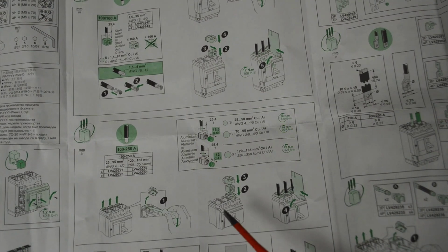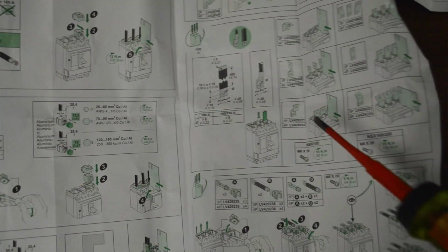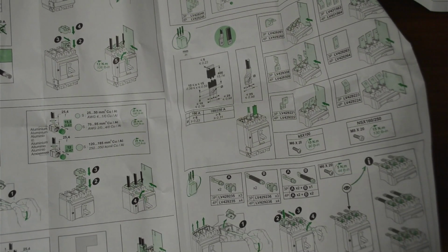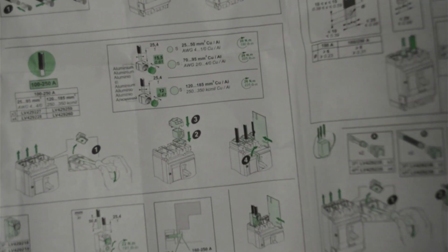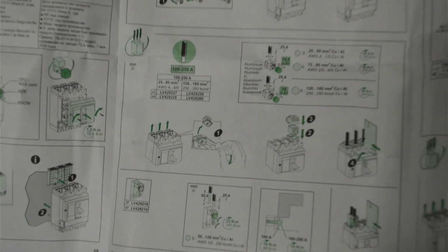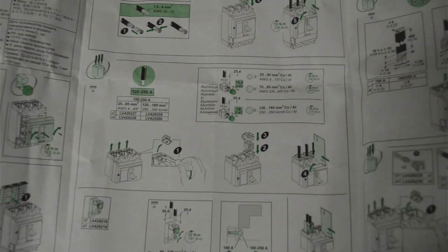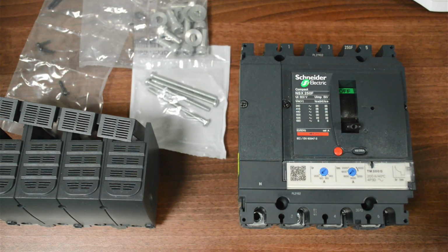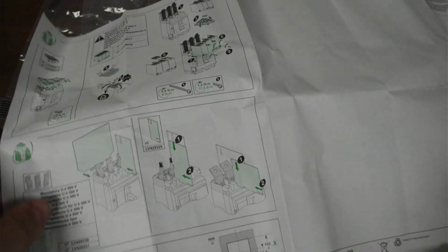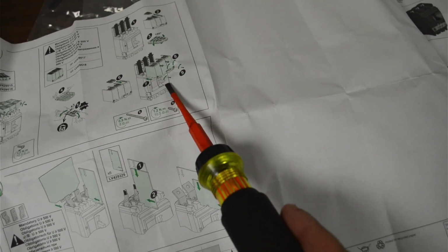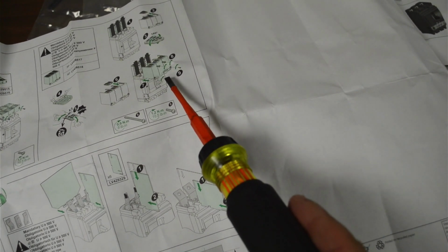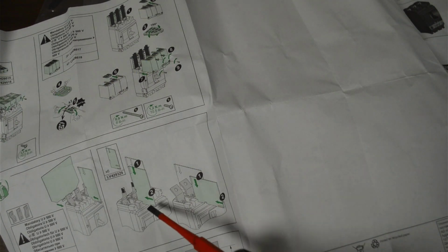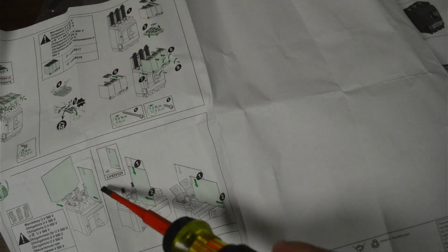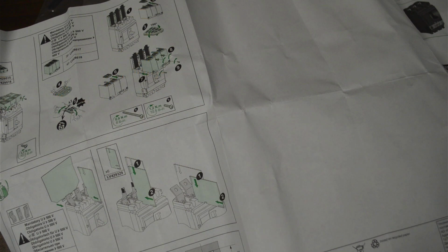There is this other great big sheet as well which explains how you can put the cage clamp in that I discussed earlier on in the video, or how you can just use your cable lugs to affect your terminations as well. So this is more the physical putting it together. Yeah, it's interesting, and I think there is a picture here which shows the cable section I was talking about. Yeah, it does. So if I turn that around there, you can see how the tunnels, tubes, whatever you want to call it, sit over the cable entry points and give you a bit of protection on that as well. You can also get these dividers that sit between the phases if you wish, or shield the outer edges and rear of the MCCB as well. So there's all sorts of things you can do.